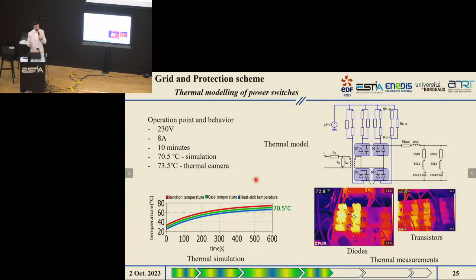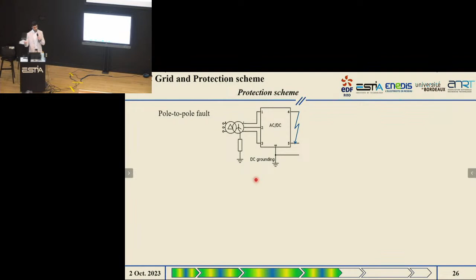Then, entering the real development and implementation of the protection scheme, it is worth looking into this subject from two different perspectives. The first one is to study pole-to-pole faults, and our proposition for protecting the system from pole-to-pole faults is to use a set of ultra-fast fuses on the input side of the grid to protect the converter and the grid itself from short circuit, and to use thermomagnetic circuit breakers, which you can see here, to protect each load feeder or each other feeder that is connected directly to the distribution system.